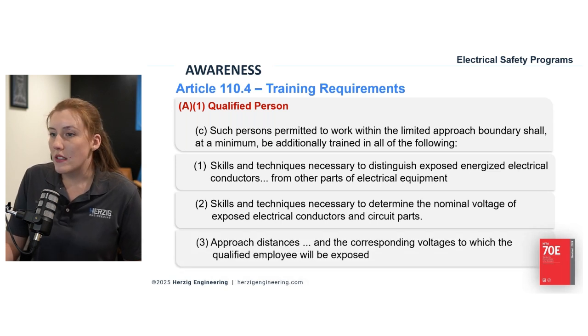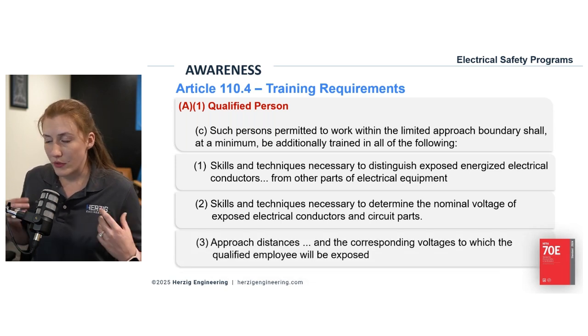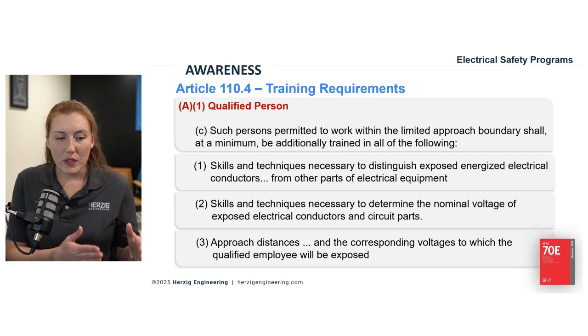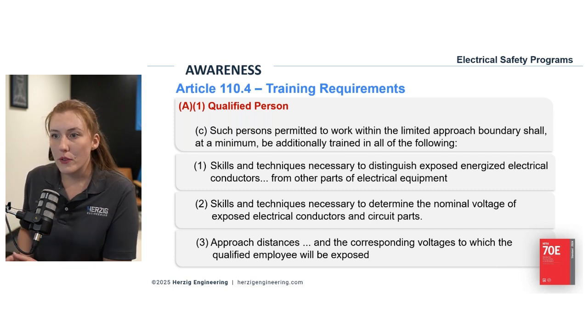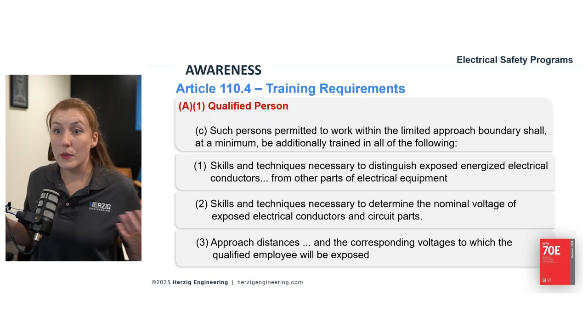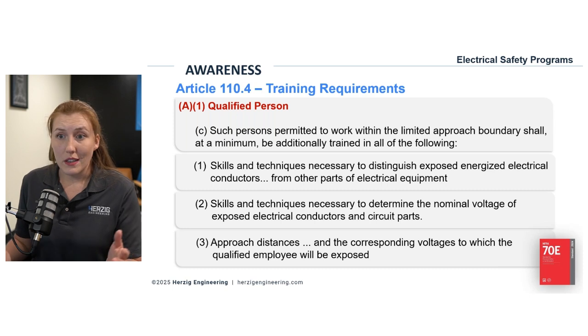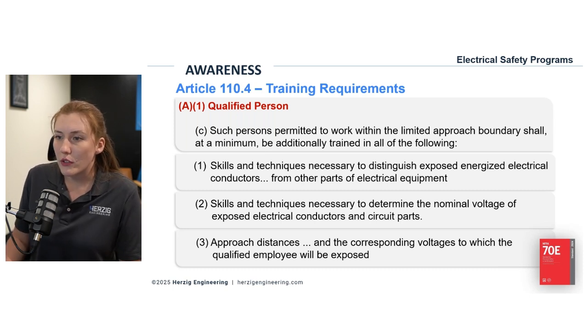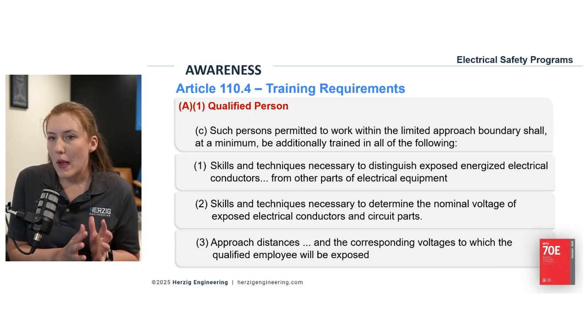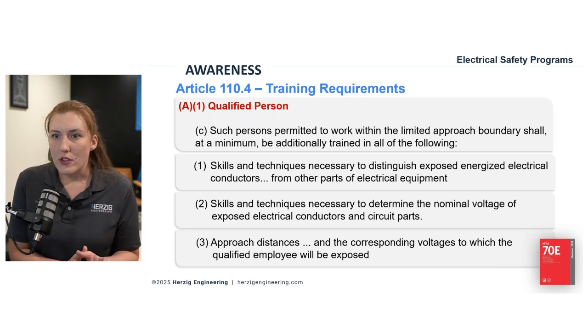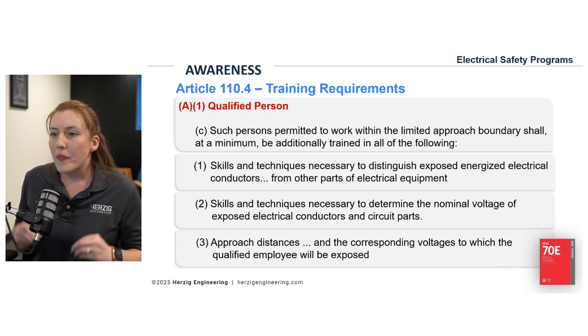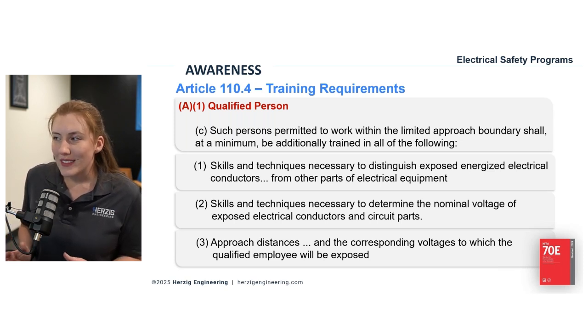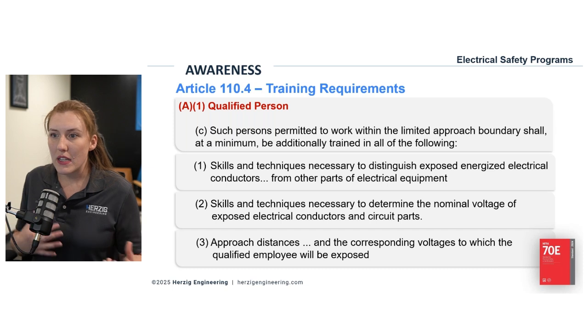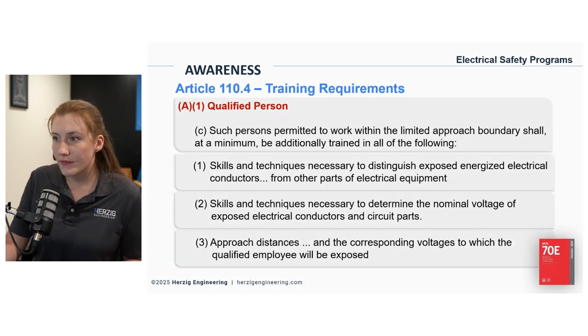What are the approach distances for those boundaries, for those voltages? Knowing what limited approach means versus restricted approach - limited approach being that everyone else has to stay back a minimum distance, so many inches or feet depending on the voltage, most of the time 3.5 feet for low voltage. Within the restricted approach boundary, you have to have your shock protection on, plus there's other additional paperwork and things going on. What are those boundaries, and what all that means needs to be covered in that training.